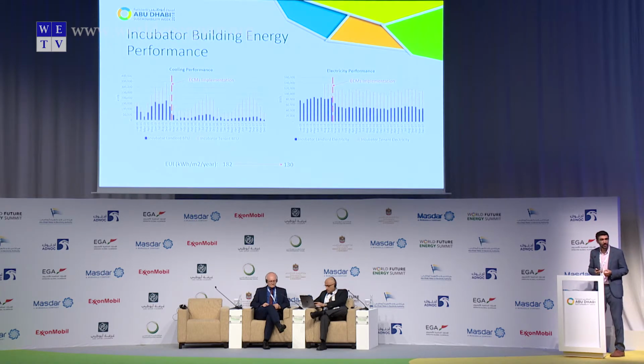This is the Incubator Building, which is a building in Masdar City. During the first year of operation, normally you cannot really have a proper consumption because the building is still in terms of commissioning, people are coming in, so you cannot really have what you like. It cannot be optimized until at least the first or second year of operation. So once we had a stable status of the building, we did an energy audit, and we discovered that we saved about 30% purely by tuning the system properly and hence reducing the gap. When we did this energy audit, the building had an energy utilization index of 182 kilowatt hours per square meter per year. After we implemented certain measures, the building is currently at 130 kilowatt hours per square meter per year. So the gap is also reduced by implementing simple measures.